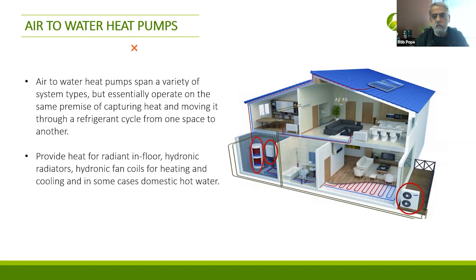That indoor unit, along with a tank, in all cases with air to water systems, you need a buffer tank. Now this buffer tank has coils in it that can be used to preheat the domestic hot water. Also heating the radiant. It does radiators, it does any kind of radiant. It also does your air because it can provide either chilled water to air handlers, ducted or not ducted, or refrigerant to, depending again on the brand chosen, it can run refrigerant to those units and provide cooling. You can also connect that system into a solar thermal array or a solar PV, but the solar PV would rarely be dedicated just to your heating system. That would be dedicated to your whole house.